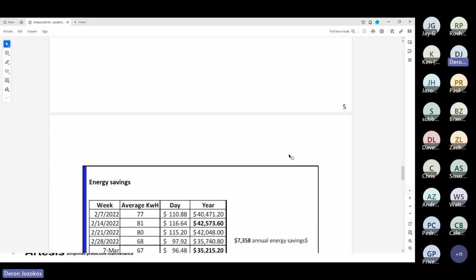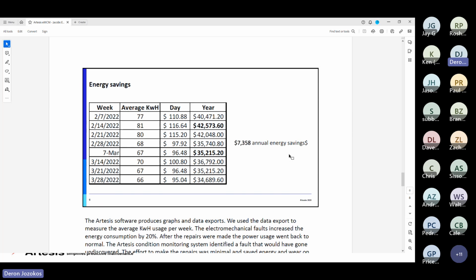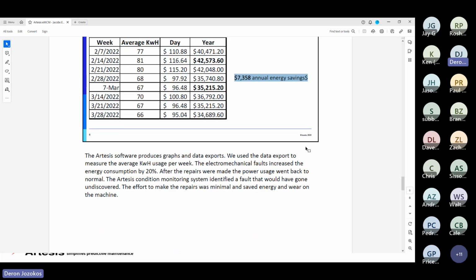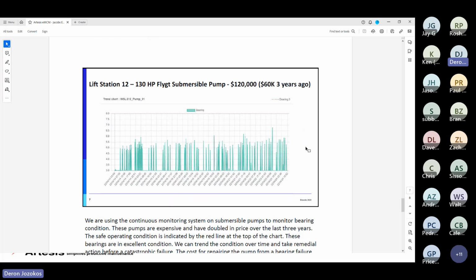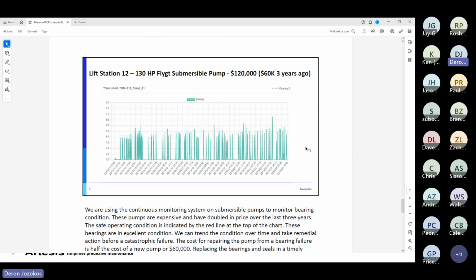Keep in mind, this was a very simple correction of re-terminating and cleaning up the copper at two positions, at the weatherhead and the MCC room. So they were able to realize over $7,300 in energy savings just by doing that. Had that had a catastrophic failure, it would have been over $120,000 to repair, replace the whole system. So a really nice case study there.